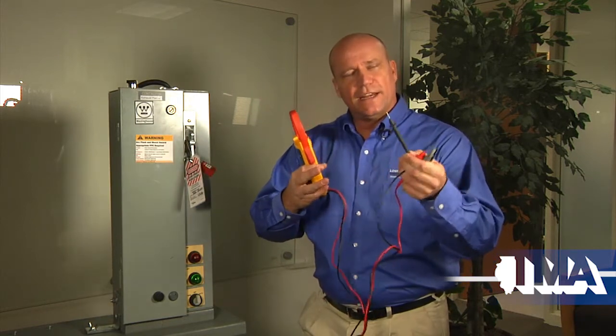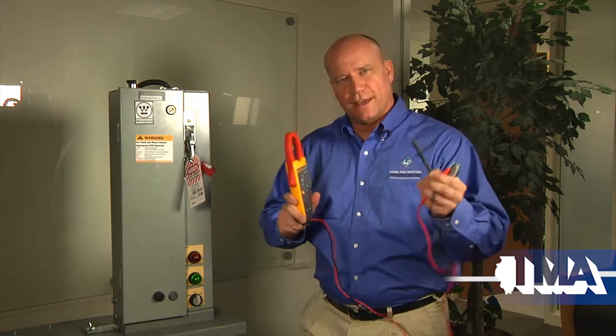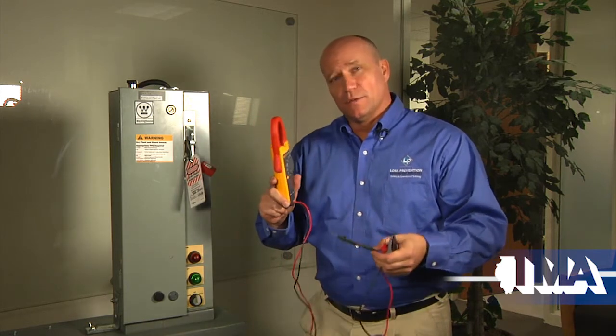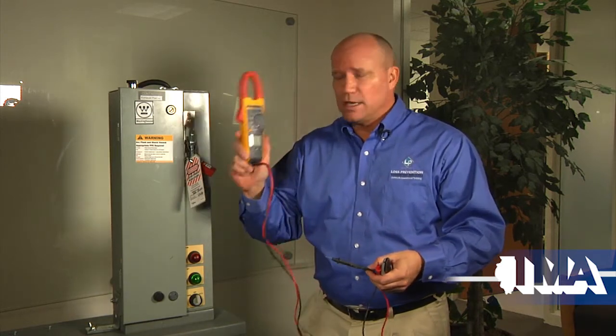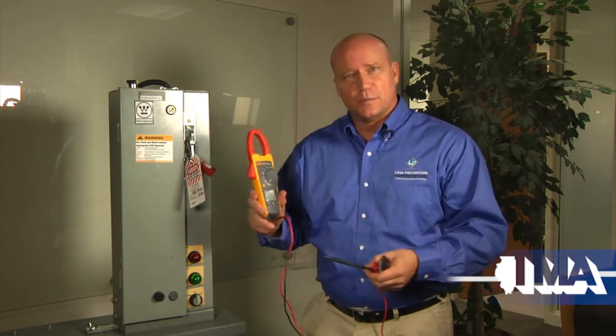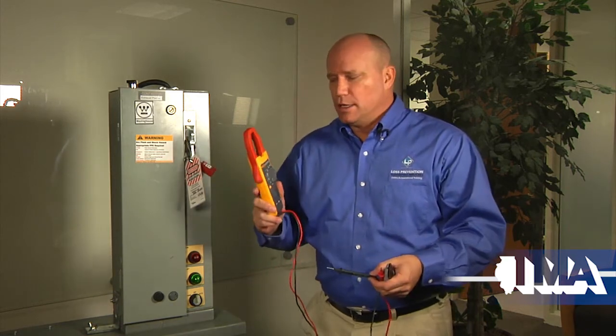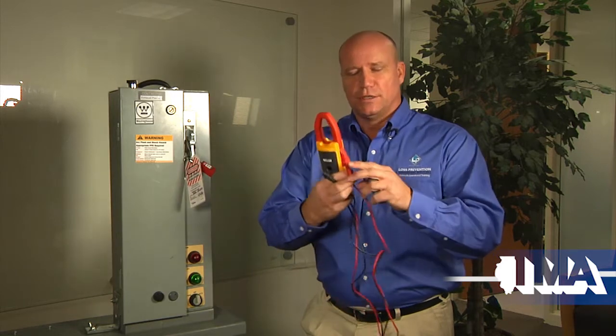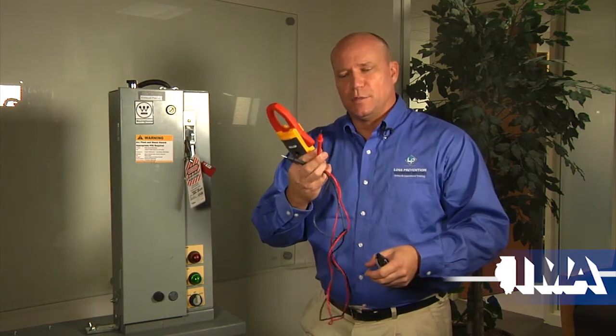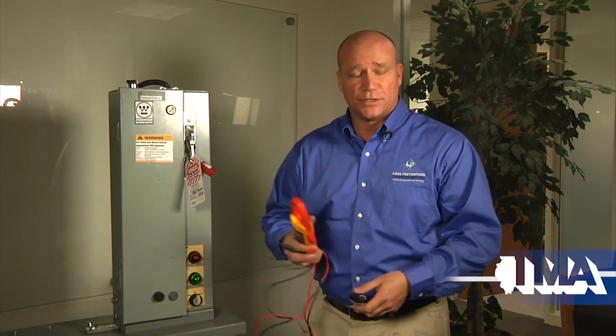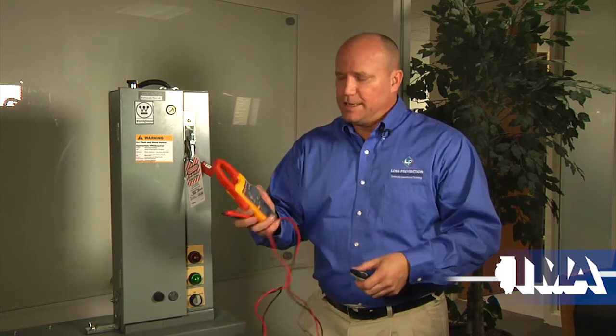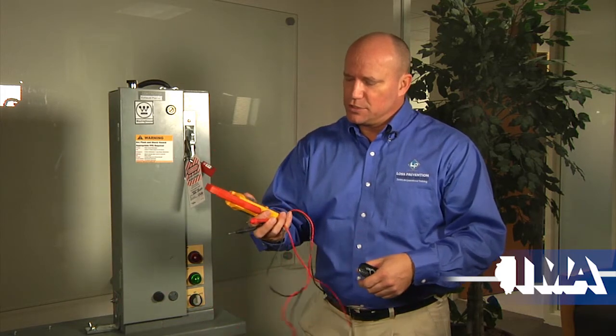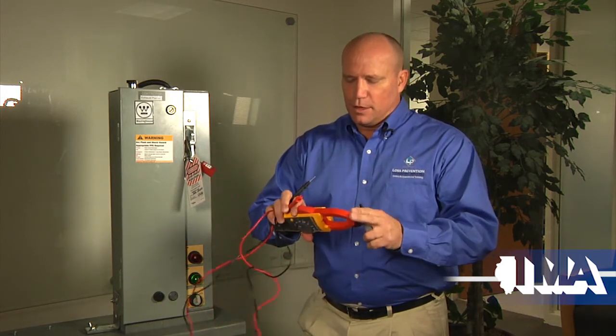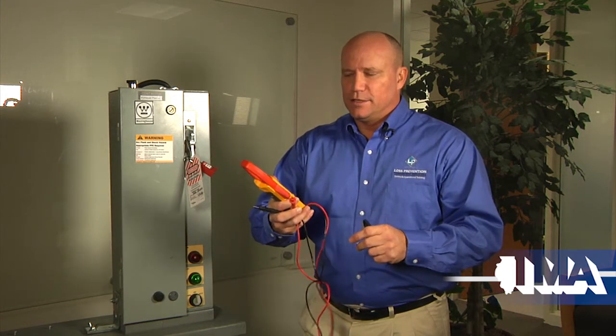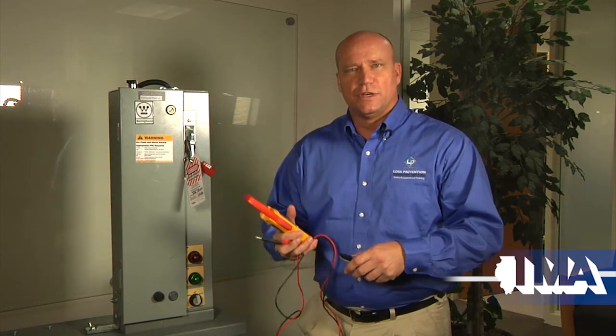So do an appropriate check on those leads to make sure they are good to go, and also that they are rated appropriately for the meter, because you can have low-rated meter leads, which may be a category 2 lead on a category 3 meter, and it's not going to protect you because the insulation is not appropriate. Also, the finger guards. These finger guards are required to be in place so that when you're doing your tests, you don't slide your fingers onto potentially live equipment. And if you do find damage after a visual check on all your equipment, make sure that you do not use it and you get a different meter.